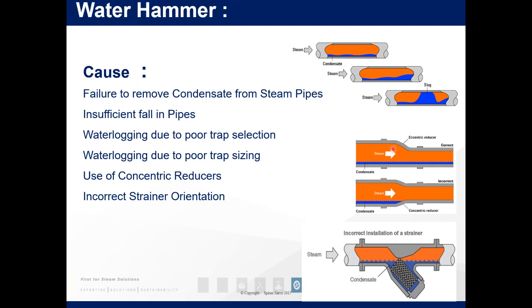So concentric and eccentric reducers. Eccentric here means that you effectively have the reduction on one side, so you maintain a straight fall in the pipe. If you have a concentric and steam is coming this way, you create a step, which effectively allows a build up of condensate. If steam was coming the other way, you wouldn't have the issue because you've got the drop.